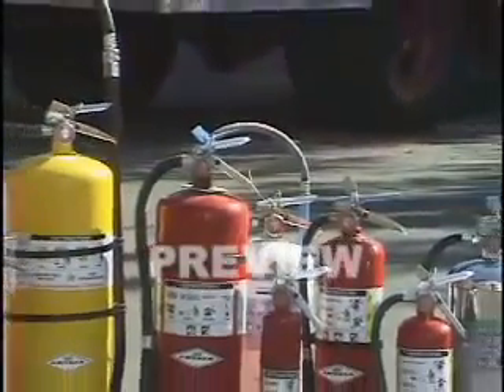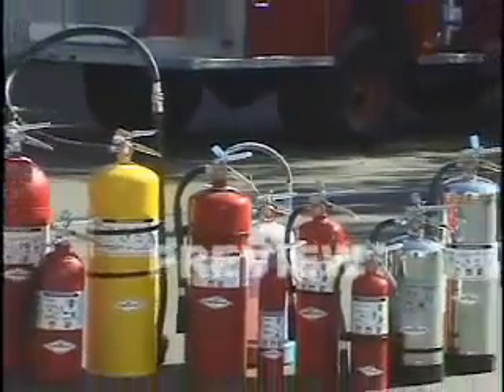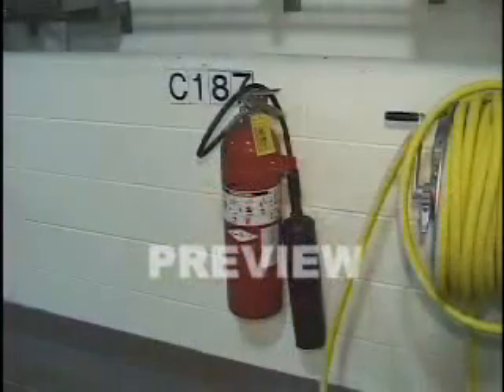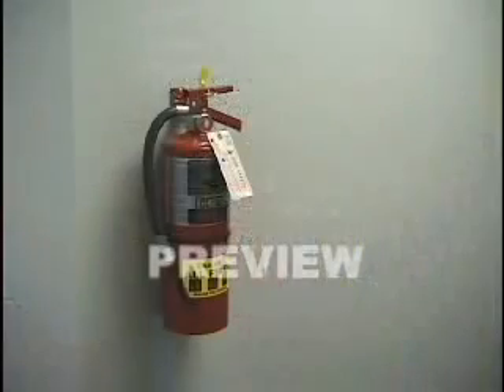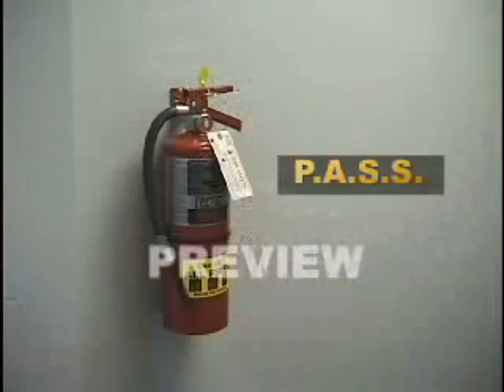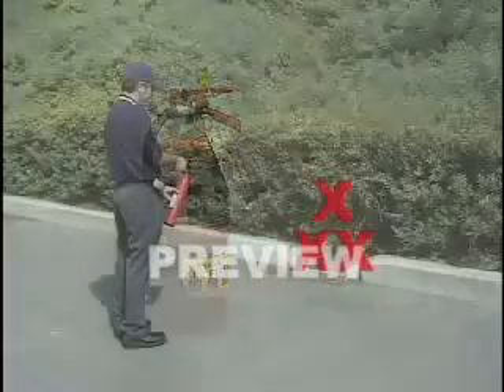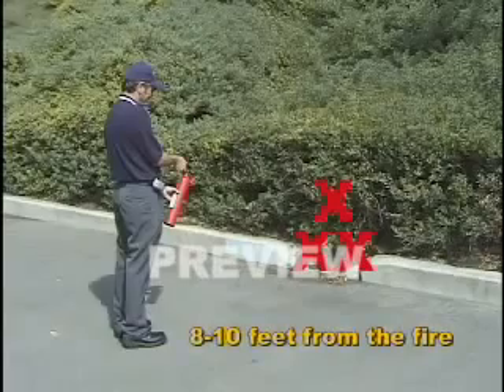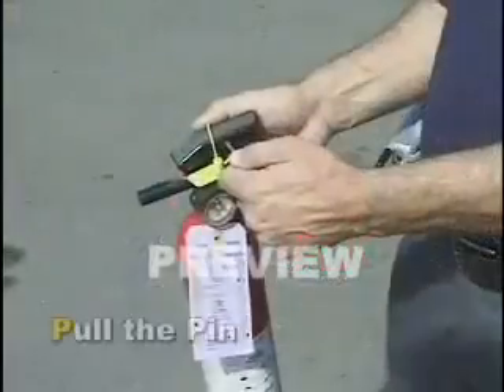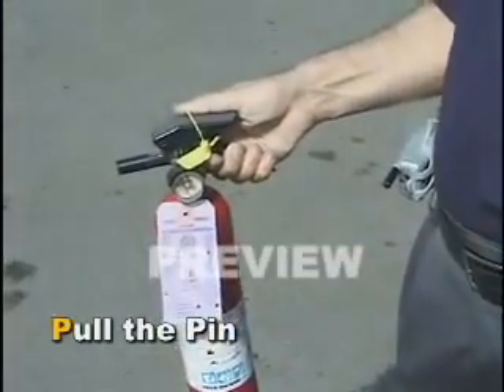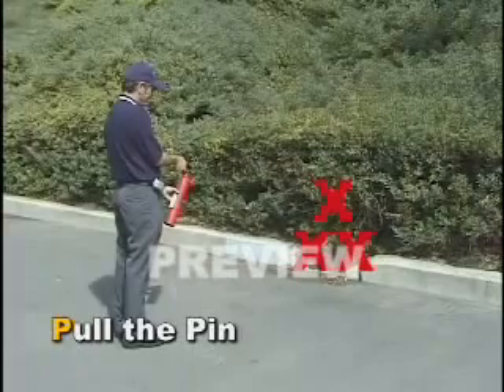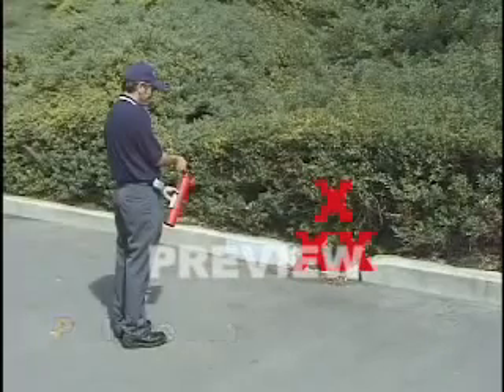If the fire can be contained or extinguished, a properly trained person should use the right extinguisher on the blaze. When using a typical extinguisher, follow the PASS method. Hold the extinguisher upright and stand back 8 or 10 feet and pull the pin. If you stand too close, the pressure from the extinguisher can actually spread the fire.